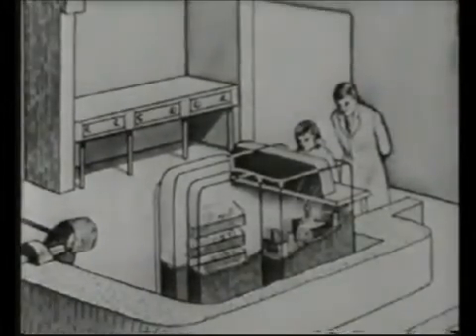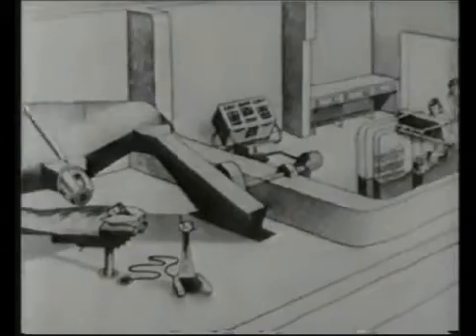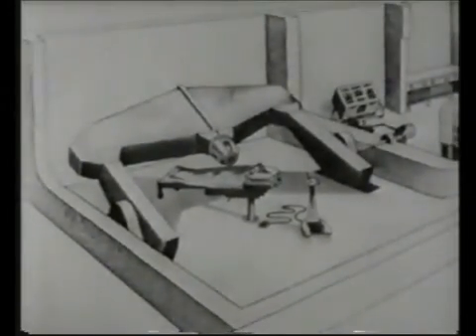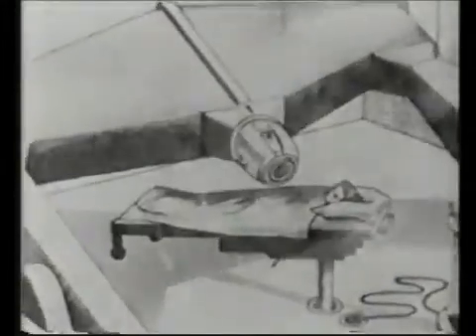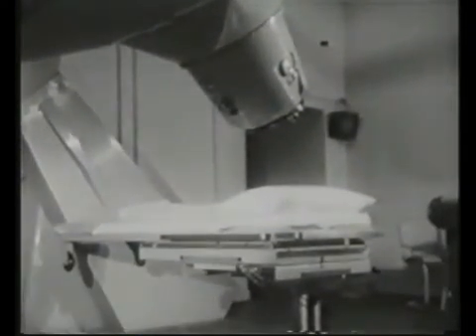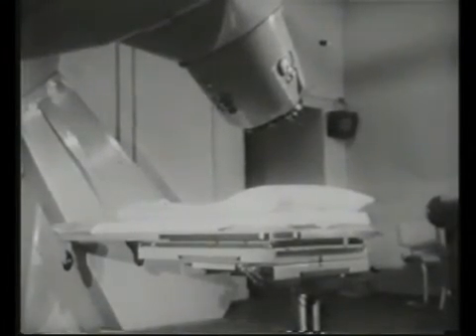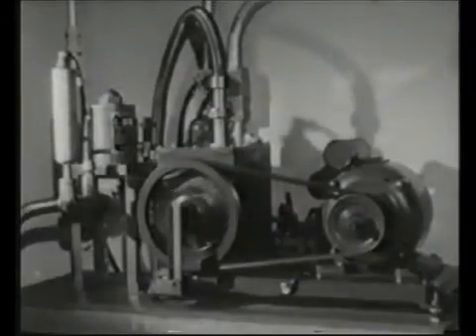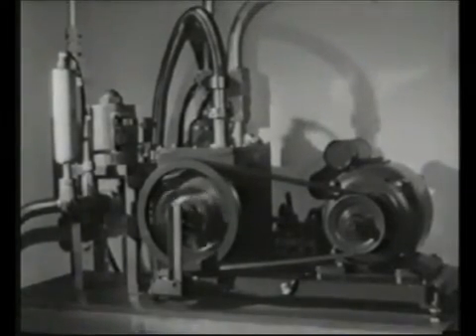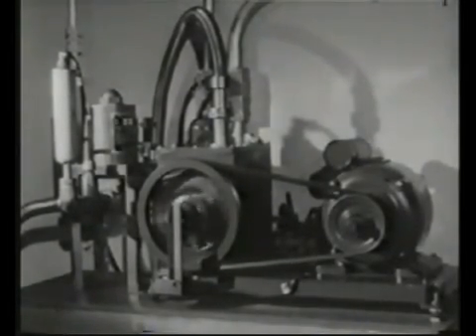Here is a drawing of a 4 megavolt linear accelerator for radiation therapy installed in the hospital at Newcastle. The magnetron and rectangular waveguides can be seen here. In this case, the machine is mounted on a gantry, which allows the X-ray head to move around the treatment table, which can be raised, lowered, rotated, and moved horizontally. In the adjoining main control room, this pump, in series with an oil diffusion pump mounted on the gantry, maintains a vacuum in the waveguide system of 1/300 millionth of an atmosphere.